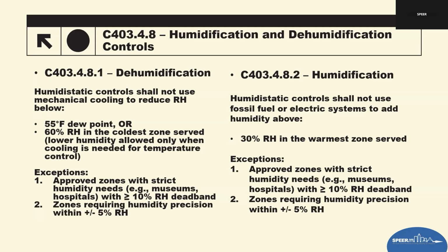However, the code does allow lower humidity if cooling is running, especially if temperature controlled and not humidity controlled. Dehumidification exceptions. There are some facilities that generally require tighter and lower humidity standards, such as museums and hospitals, clean rooms, labs, archive storage. These zones must have at least a 10% relative humidity deadband, so it ensures equipment is not constantly cycling off and on. The second exception allows for spaces that meet strict humidity standards, within plus or minus 5% relative humidity, to use more precise control strategies when required by the code.